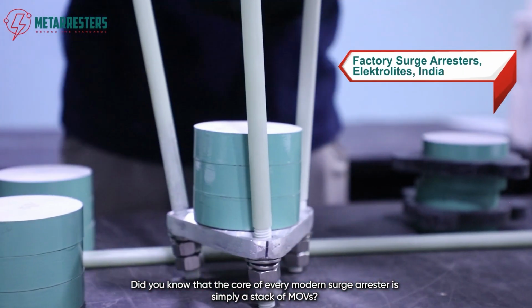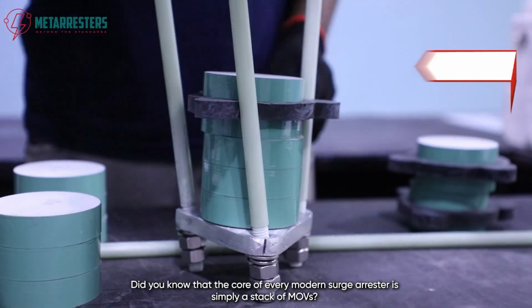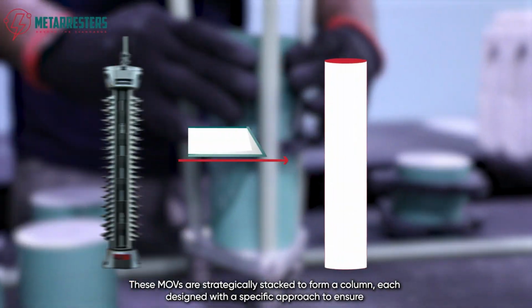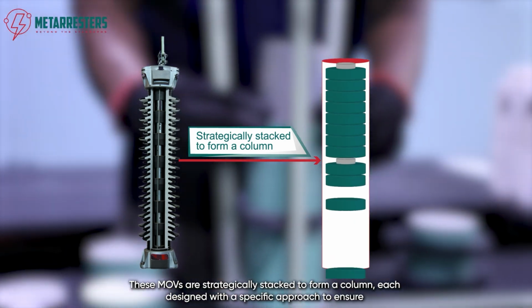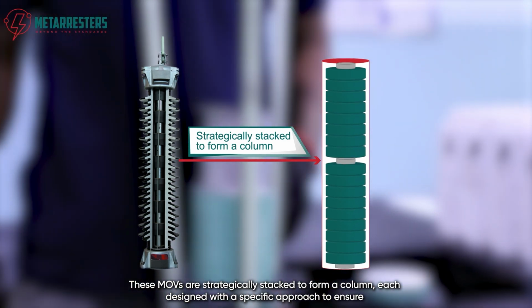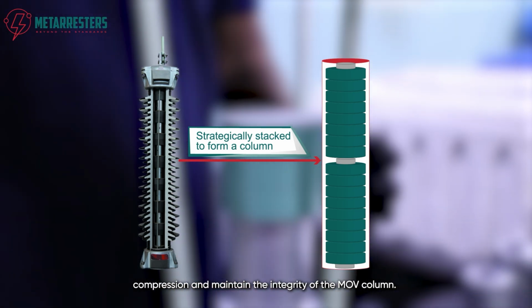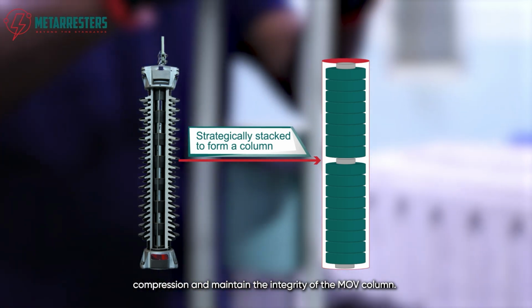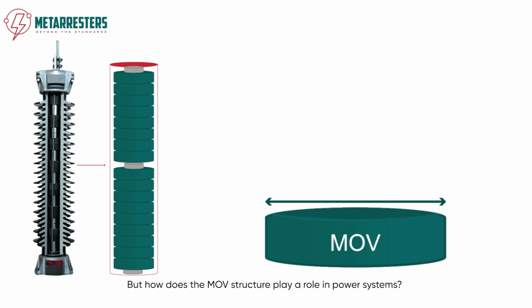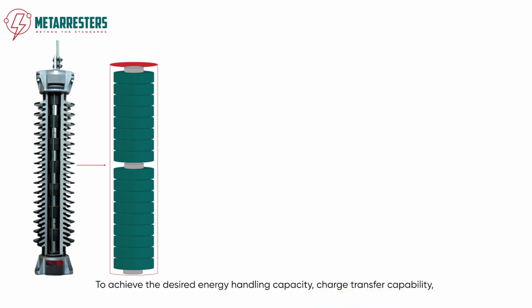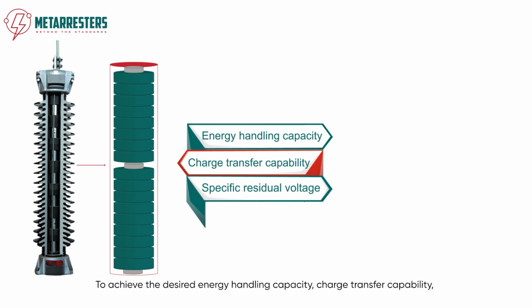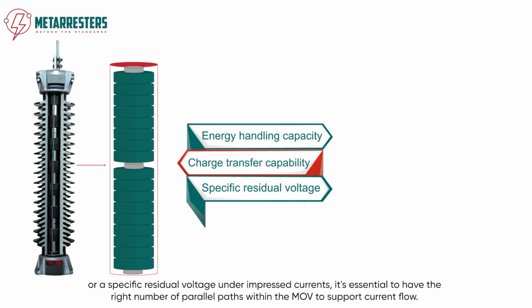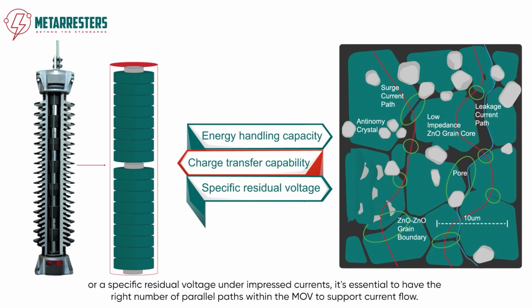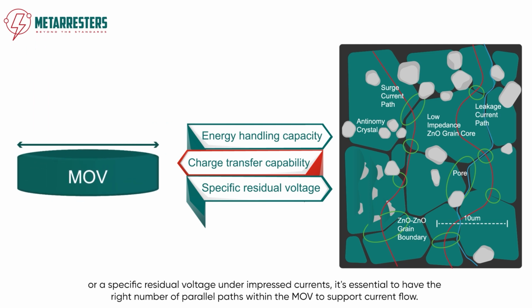Did you know that the core of every modern surge arrestor is simply a stack of MOVs? These MOVs are strategically stacked to form a column, each designed with a specific approach to ensure compression and maintain the integrity of the MOV column. But how does the MOV structure play a role in power systems? To achieve the desired energy handling capacity, charge transfer capability, or a specific residual voltage under impressed currents, it's essential to have the right number of parallel paths within the MOV to support current flow.